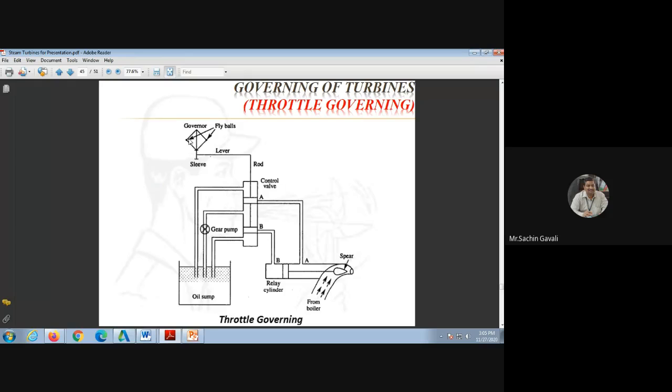आणि जर स्पीड कमी झालं तर स्टीमचा फ्लो वाढवायचा, जेणेकरून टर्बाईनचं स्पीड वाढेल. तर हे गव्हर्नर आहे, सेंट्रिफ्युगल गव्हर्नर. याच्यामध्ये जर गव्हर्नरचं स्पीड कमी झालं तर इथले बॉल्स कमी वेगानं फिरतील, आणि बॉल्स कमी वेगानं फिरल्यानंतर ही स्लीव कमी वेगानं फिरल्यामुळं खालच्या बाजूला राहते आणि त्या केसमध्ये स्टीमचा फ्लो कमी वेगानं पडते. जर आपल्याला स्पीड वाढवायचं तर स्टीमचा फ्लो वाढवला, लिव्हर खाली आलं तर गव्हर्नरचं स्पीड वाढतं.